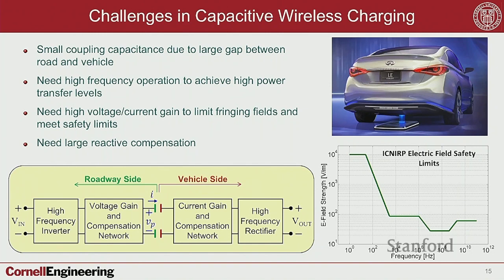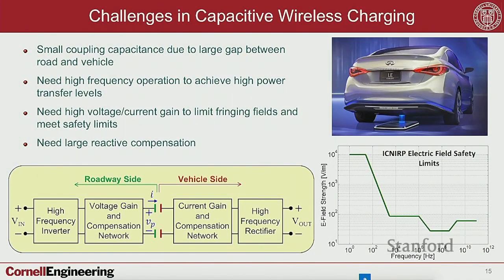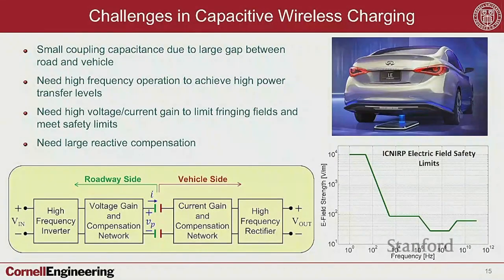First, we have to cross the barrier of the air gap. Another target was that we had to do this at 50 kilowatts per meter squared for the ARPA-E goal — meaning if we had a meter, we'd need to deliver 50 kilowatts through it. Our target was a 1 kilowatt system, so we had proportionately less area, meaning we had to deliver 1 kilowatt through about 6 picofarads of capacitance, which is tiny. That was a huge amount of reactance across which we had to deliver this energy.